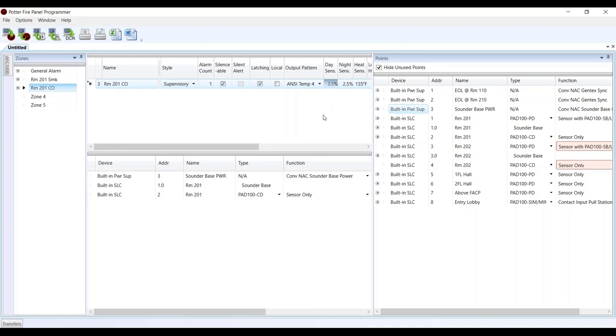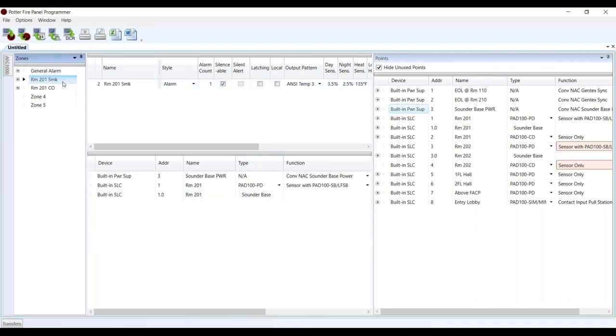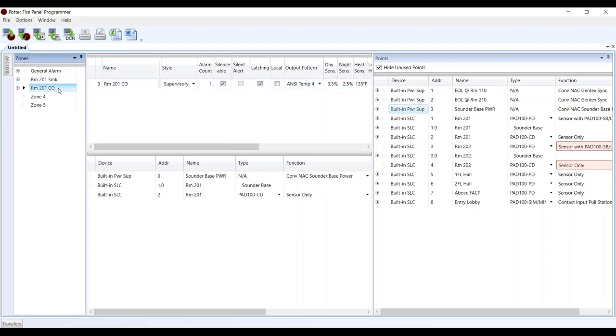The other thing I forgot to change is the output pattern — that's going to be temporal 4 for the CO detector. So if there's a general alarm in the building, both sounder bases will do temporal 3. If the smoke detector in the room activates, we do temporal 3 just on the sounder base inside the room — local only. If the CO detector activates, we get temporal 4 from the same sounder base. If the CO is active and then the smoke goes into alarm, that takes precedence and switches over to temporal 3 — smoke detectors always have higher priority.